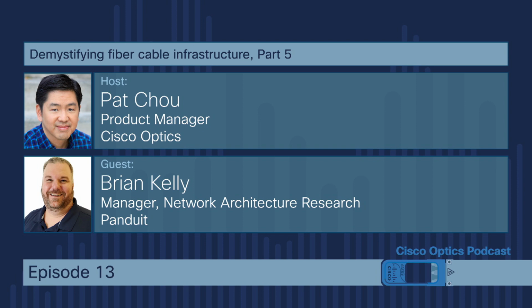We had to do this with a lot of the older Catalyst switches and some older Nexus switches because they were side-to-side breathers. When put into a data center, airflow is front to back—hot aisle, cold aisle. So we made special ducts that would pull from the rack unit above the switch and below the switch, funnel it to the side, across the switch, and exhaust out the other side to the back of the cabinet.